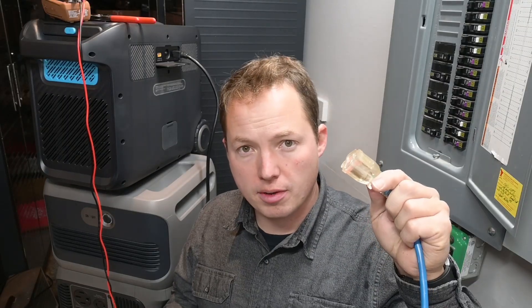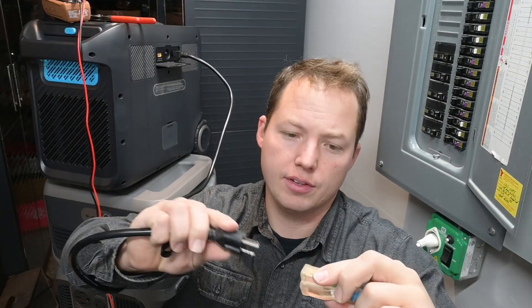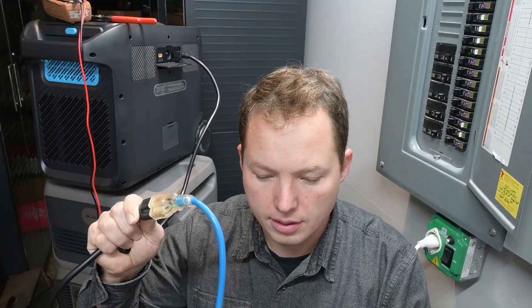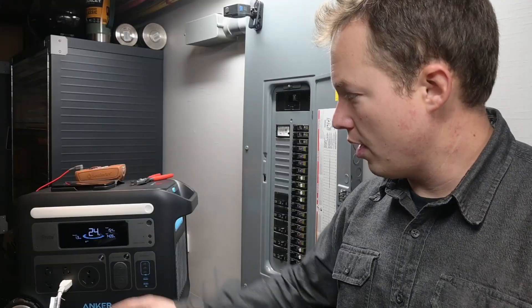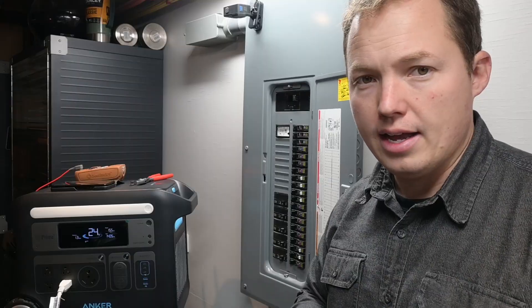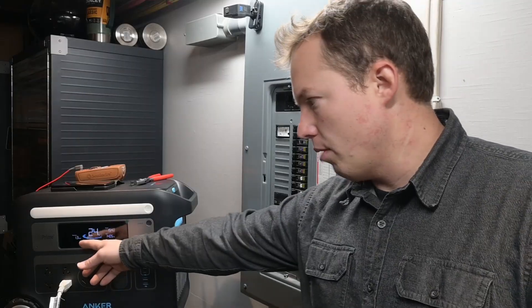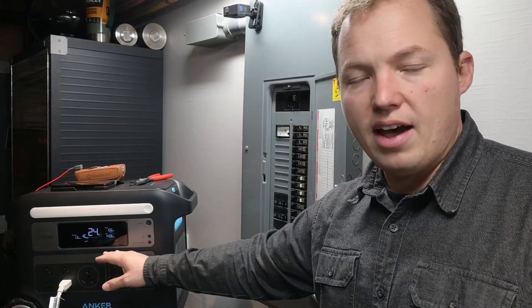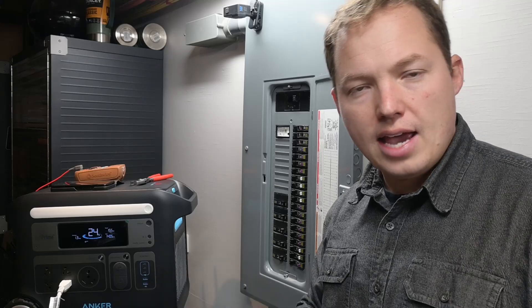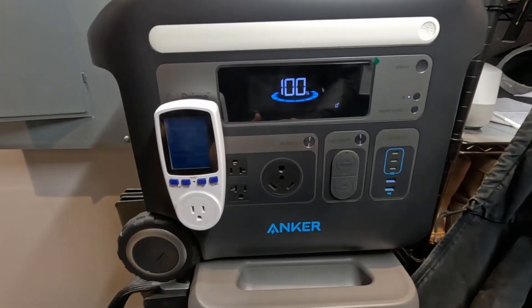We now have our power source coming from our gas generator outside, connected to the grid input on the back of the Anker Solix F2000. The generator is ramping up and this is working exactly as hoped: we're inputting 1400 watts and simultaneously outputting 155 watts to the furnace fan. It's saying 1.3 hours to go from 25 percent to 100 percent, meaning we only need to run the generator for a couple of hours a day rather than 24 hours continuously.